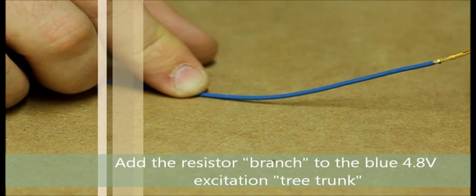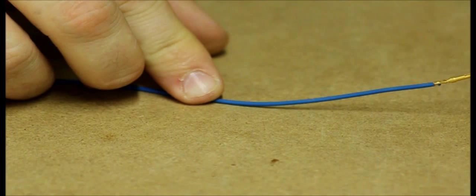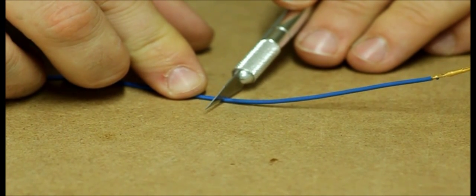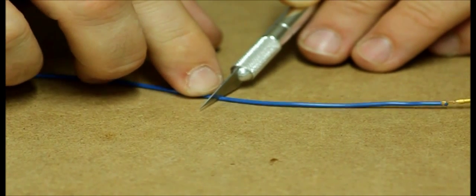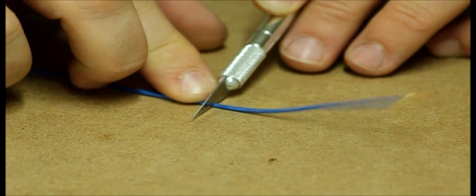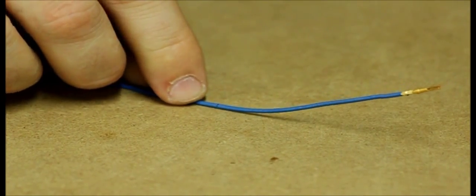Step number one: take the 4.8 excitation wire, remove it from the connector. Take an exacto knife with a relatively sharp blade, set it on the sheathing, press gently and roll the wire underneath the blade. This will cut the sheathing, but don't press so hard that it will actually cut the wire.